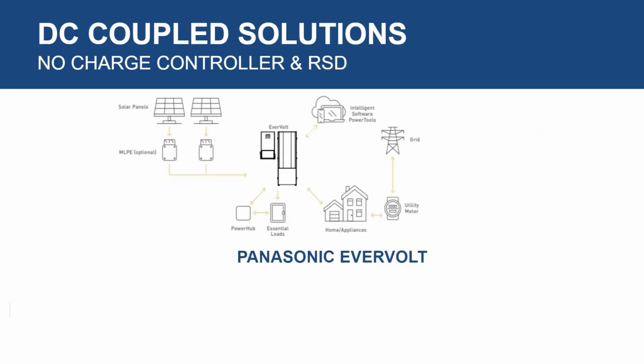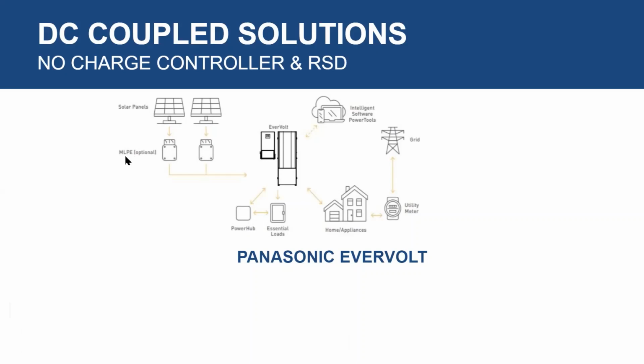Panasonic EverVolt, very similar solution. Solar panel, here it says module level power electronics optional. Since we're thinking about this as a DC coupled option, we're just going to go straight from the solar panel into the EverVolt solution. If you need rapid shutdown, you can throw in an APsmart rapid shutdown compliant device. That would work. We're feeding our EverVolt with DC from our PV, with DC from our battery, and then you're feeding your essential loads alternating current. So really, this slide is going to be solutions that have your typical DC input where rapid shutdown would be from a third party.